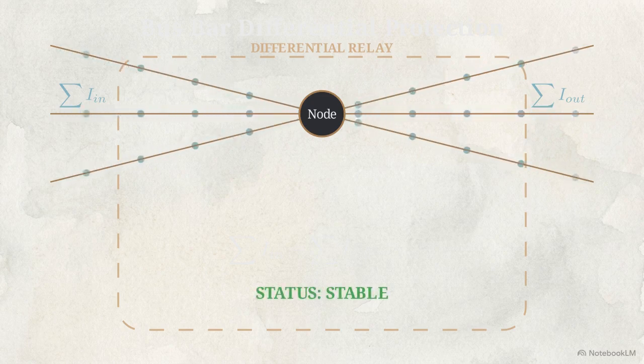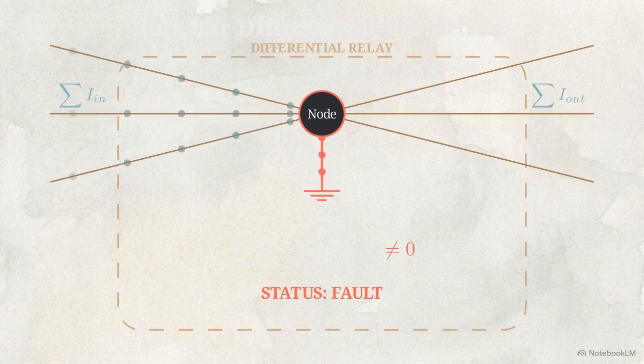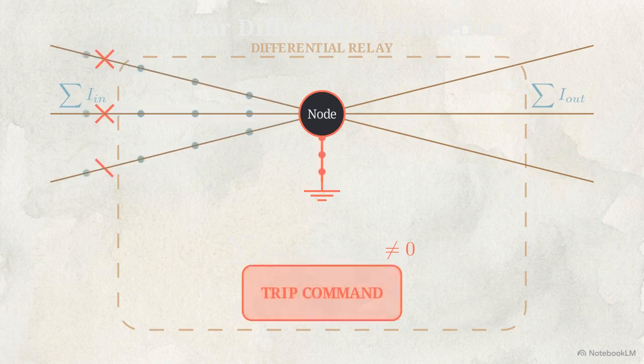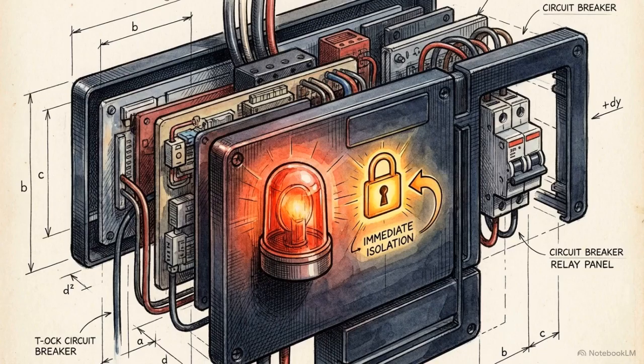A differential relay continuously monitors the entire array, mathematically summing all incoming current against all outgoing current. Under normal conditions, whatever current enters the node must exit the node. If the sum equals exactly 0, the system knows it is perfectly stable. But if a short to ground occurs inside the bus zone, current violently leaks out. The sum instantly becomes non-zero, and the relay triggers a localized breaker trip within milliseconds. Topological redundancy provides an alternate path, but it is this high-speed mathematical protection that ensures the grid survives long enough to use it.